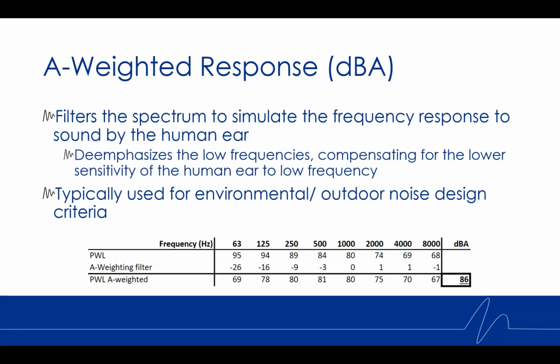So we have a sample calculation at the bottom here. The sound power level numbers, that's the first row. That's typical for a piece of equipment. That's the sound energy at each frequency from the unit. We're filtering those. Those are a standard set of numbers. And then we have our A-weighted numbers at the bottom. And without going into too much detail here, those are all added up logarithmically to get us one final dBA number, which is 86.